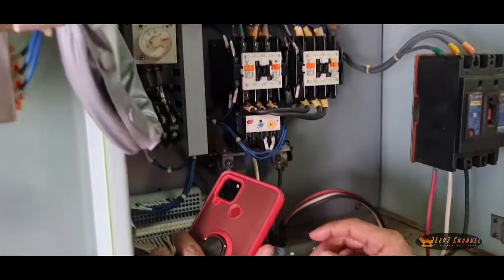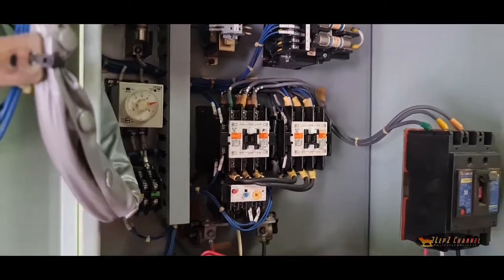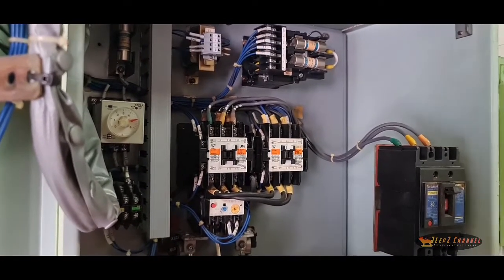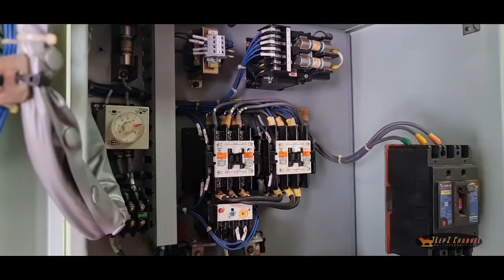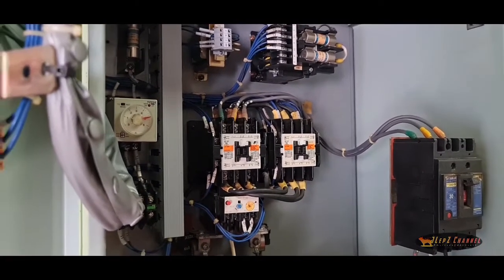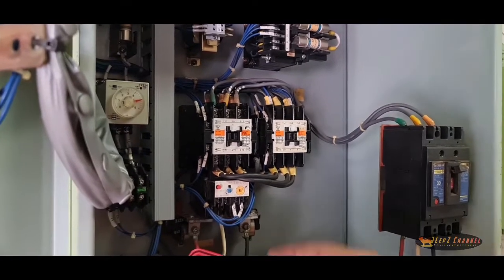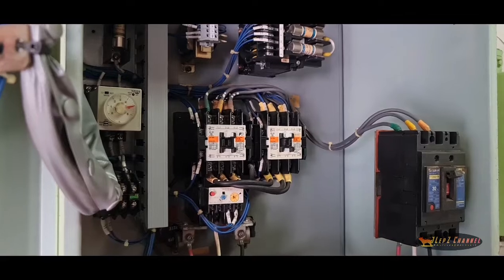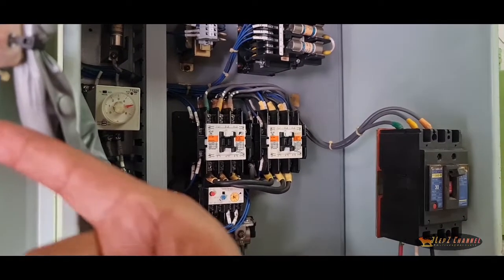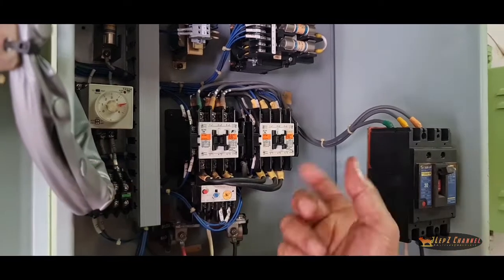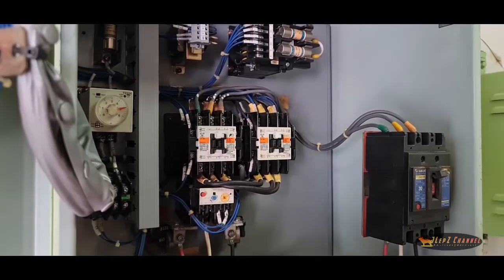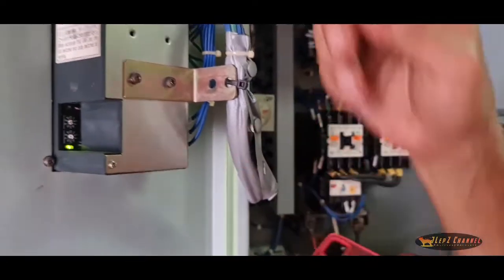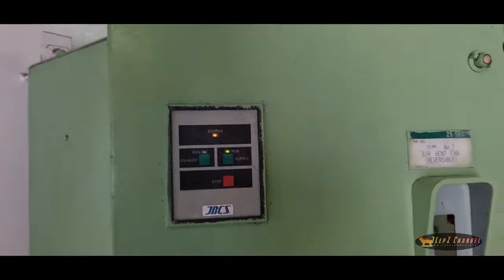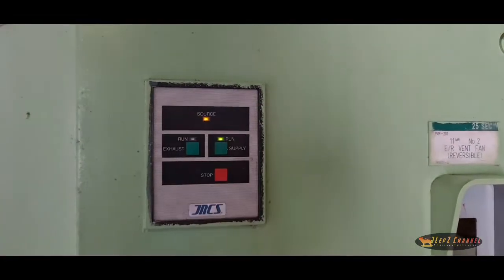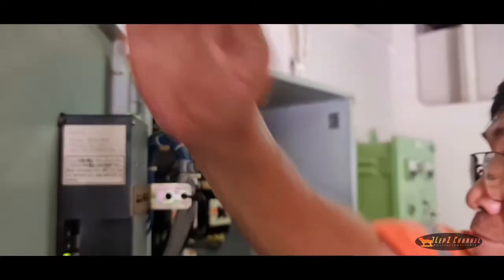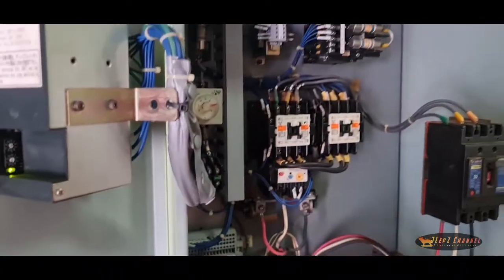The only problem is that the duty engineer at night time will always come down to the engine room because there is an alarm. This switch comes from here. But there is nothing to worry about, because every time it tripped off, it also ran by itself. The control of this engine room fan is electronic type. Here in the front, see, this is digital type control, 18 volts control circuit.